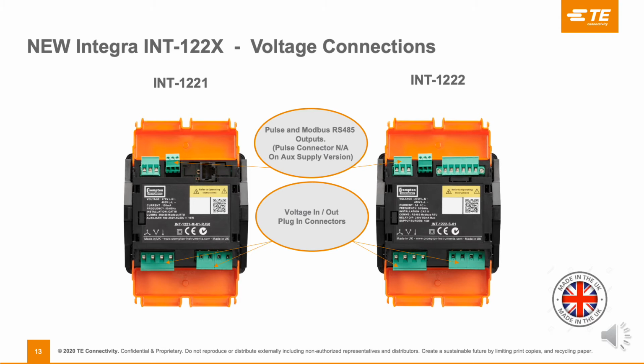As we mentioned before, if it is an auxiliary powered meter, the pulse changes to the auxiliary connection terminals, which is clearly identified on the label. At the bottom of the meters, there are plug-in connectors as well for ease of installation. You've got a voltage in and voltage out connector. So once you've got your three phases into one of the panels, you can then daisy chain in to out for the voltage. So there's no requirement for separate fuses and separate wiring for each outgoing way. You can basically daisy chain all the way down the panel, voltage in, voltage out, and it will power the meter as a three-phase unit.